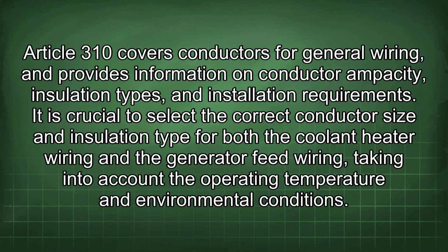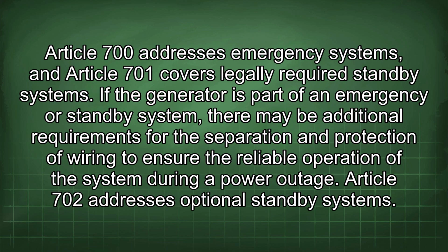Article 310 covers conductors for general wiring and provides information on conductor ampacity, insulation types, and installation requirements. It is crucial to select the correct conductor size and insulation type for both the coolant heater wiring and the generator feed wiring, taking into account the operating temperature and environmental conditions. Article 700 addresses emergency systems, and Article 701 covers legally required standby systems. If the generator is part of an emergency or standby system, there may be additional requirements for the separation and protection of wiring to ensure the reliable operation of the system during a power outage.